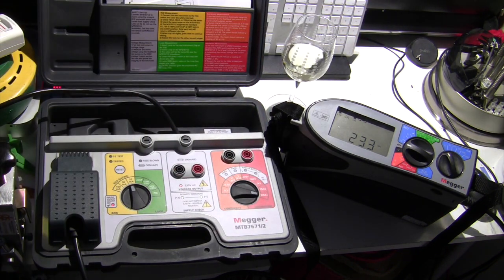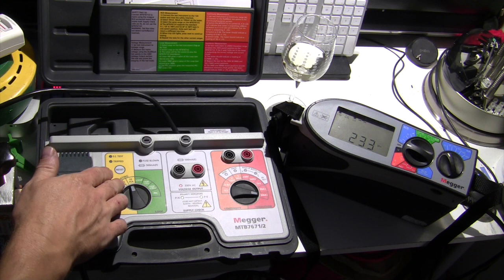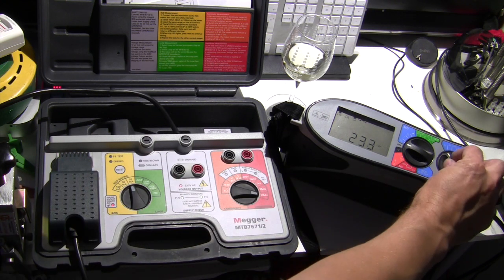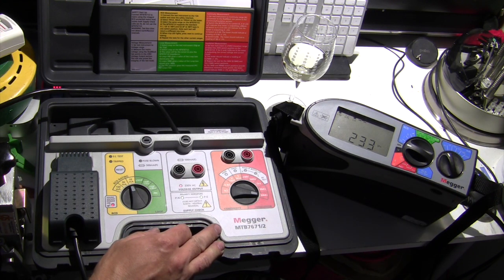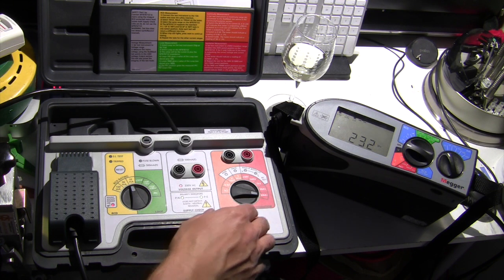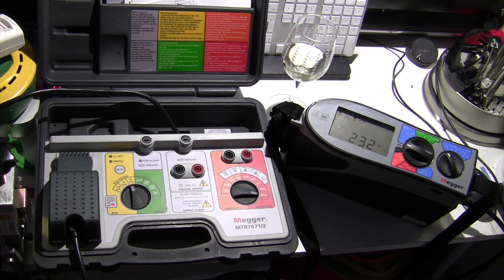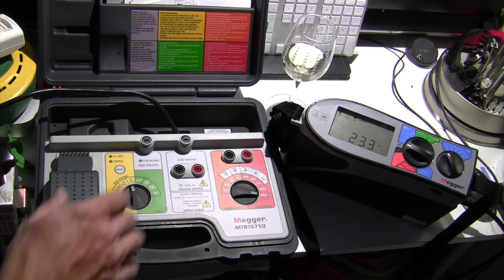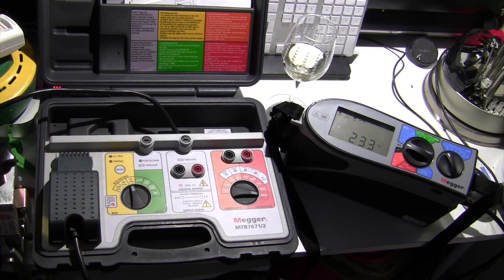So off we go. First of all, we're on the 10 milliamp range. I've set the tester to 10 milliamps as the RCD I'm going to test, and we're going to send in a half times rated current. So we're going to send 5 milliamps down the line, and what should happen is this should not react. It should not be enough to trip that RCD, or that simulated RCD.